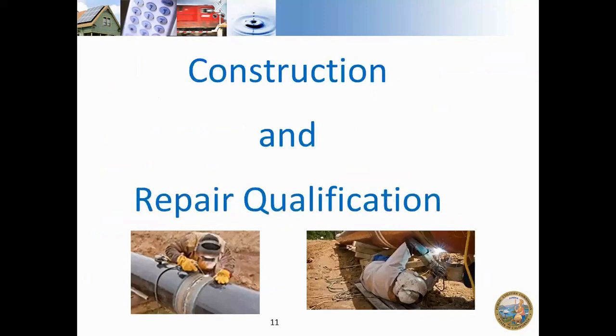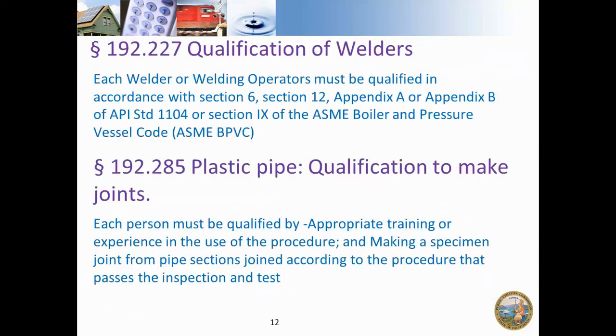There are particular qualifications that apply to steel pipelines and plastic pipelines. Some regulations address the qualification of welders — welders should be qualified according to Sections 6 and 12 of API 1104. This is not required for mobile home parks since most of them are plastic pipe, but if you have any steel pipe needing welding and use a contractor, you need to make sure their personnel are qualified.